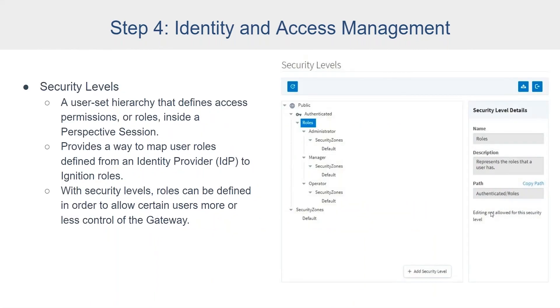Security levels are a new concept as of Ignition 8.0. They are a user-set hierarchy that defines access permissions or roles inside a Perspective session and throughout the rest of Ignition as well. They provide a way to map user roles defined from an identity provider to Ignition roles, or to create your own custom security tiers. With security levels, you get an inheritance model where more specific security levels have more generic security levels above them. For example, all employees can access a page in read-only mode, but only plant floor operators can read-write. Since plant floor operators are employees, they get everything under the employee security level plus their own — so a supervisor has more privileges but also inherits all operator privileges.